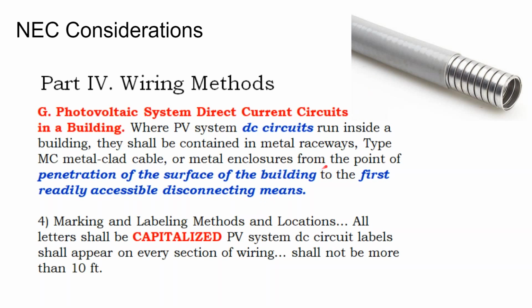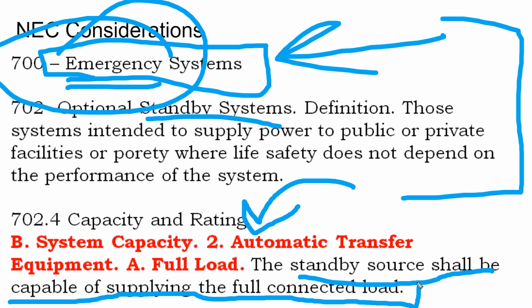And so that's why with your StorEdge, with your grid-tied battery systems, they say, oh, we're going to have an automatic transfer switch built into our inverter, and you're going to install a dedicated load panel with just a few loads that you're trying to power, and that's going to be our standby power source. Because you can't just put a 40 amp standby power generator on a 200 amp electric service, because you're not going to be able to supply the load. The AC turns on, it sucks all the electricity out of the wires for the rest of your circuits, and your whole power system goes out. It's undersized for the standby system you're trying to power.